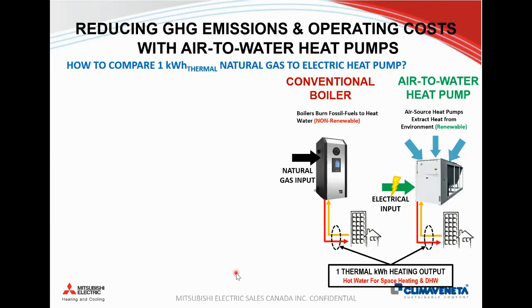So I just want to go into the operating side of it, and then we'll talk about a case study. If we want to compare operating costs for natural gas supplying the same amount of heat, it's the same amount of heat provided to the building, whether it's provided from the heat pump or the natural gas boiler.